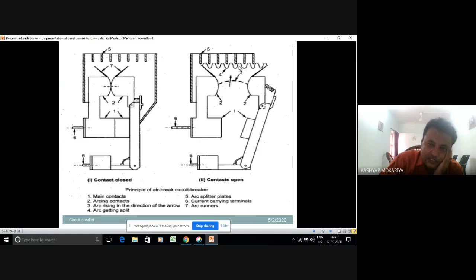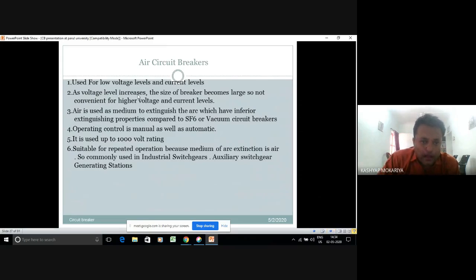But the principle which is used in a DC breaker or in a low voltage AC circuit breaker, can it be used in a high voltage breaker? No, because for a high voltage breaker, if you use the same phenomenon of lengthening the arc, the size of the breaker will be very high. In the earlier slide, I was using the words arc runners and arc splitters. So arc splitters is this number 5. We have multiple plates here: plate 1, plate 2, plate 3, plate 4, plate 5, plate 6. When through the arc runner your arc enters the splitter zone, due to R equal to rho L by area, due to the lengthening of the arc, it starts cooling. So this was the basic principle of an ACB, which was used for LT motors of 90 to 160 kilowatt, the air circuit breaker.